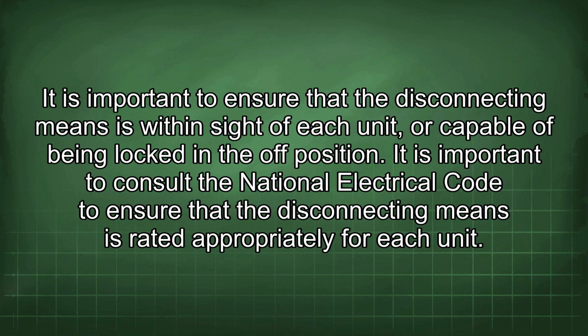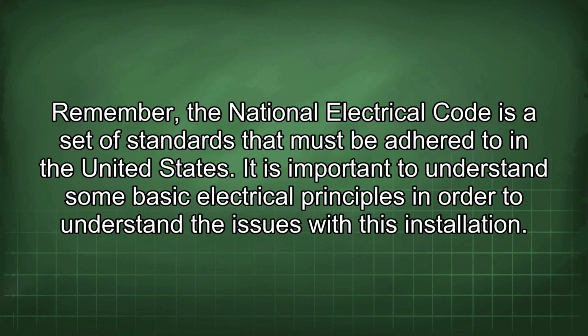It is important to ensure that the disconnecting means is within sight of each unit, or capable of being locked in the off position. It is important to consult the National Electrical Code to ensure that the disconnecting means is rated appropriately for each unit. Remember, the National Electrical Code is a set of standards that must be adhered to in the United States.